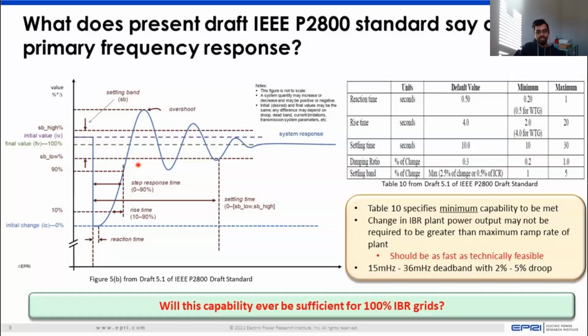So for some resources, this value may be a certain value. For some other resources, based upon different constraints, it might be a slower value. But it's dependent upon the resource that is providing this response. And that's something which is very important, which we will see next. And the standard values with respect to deadband are 15 to 36 millihertz and a 2 to 5% droop.